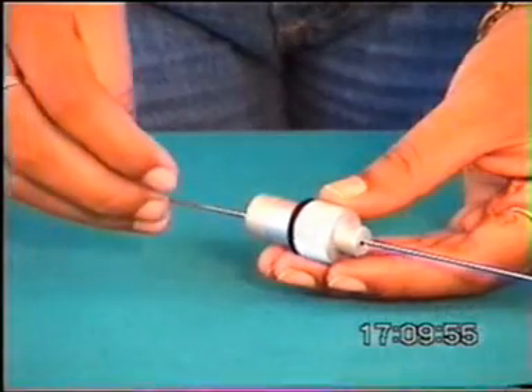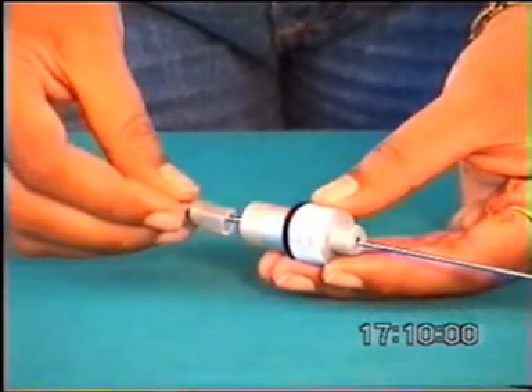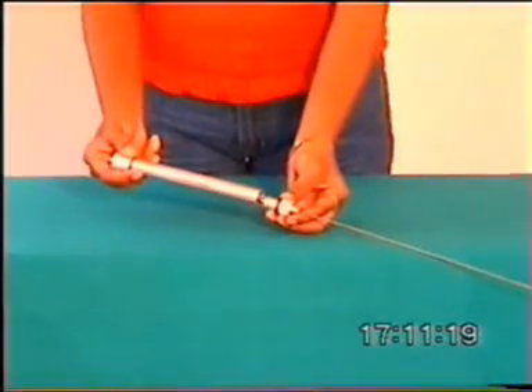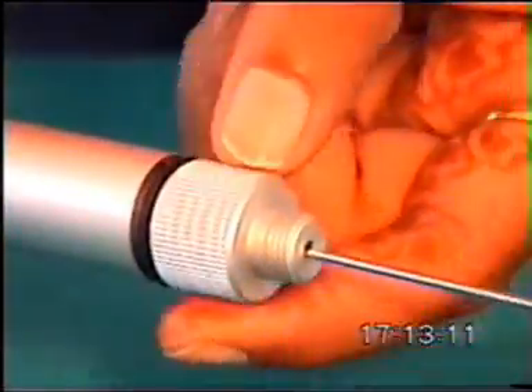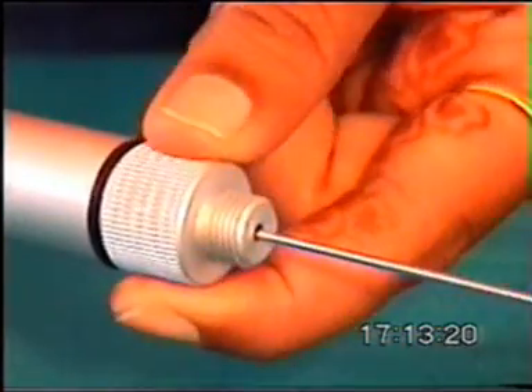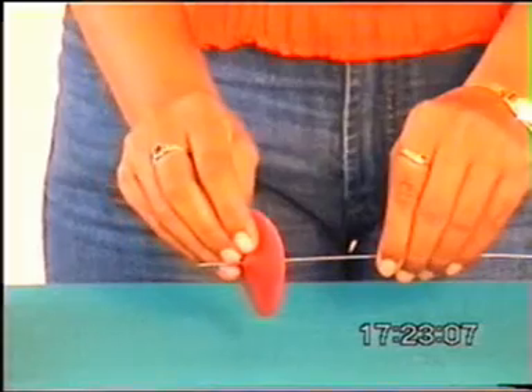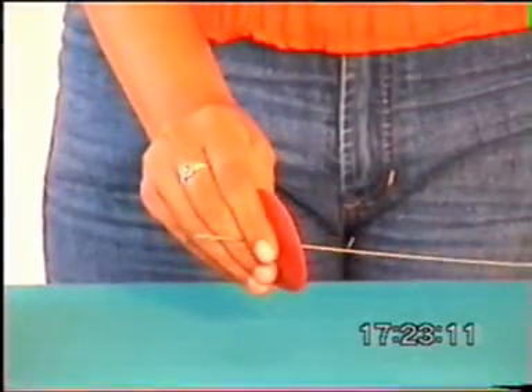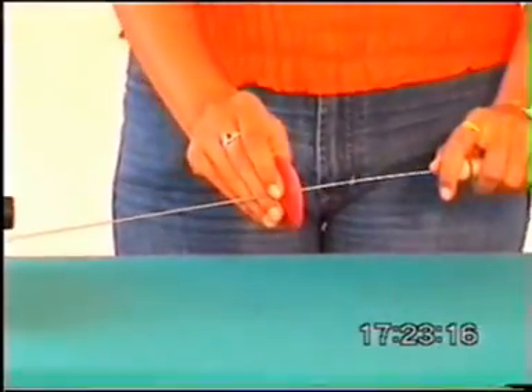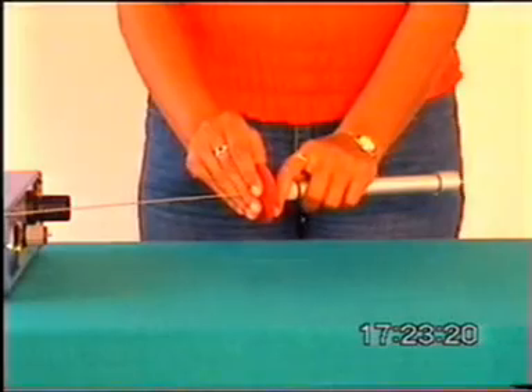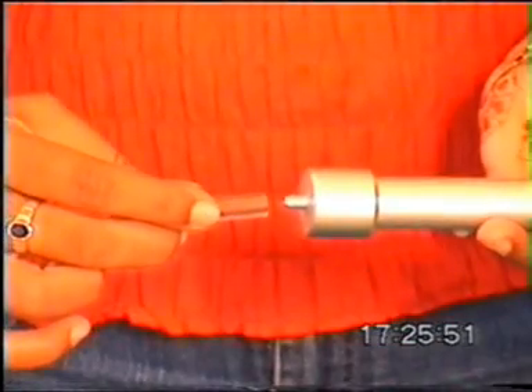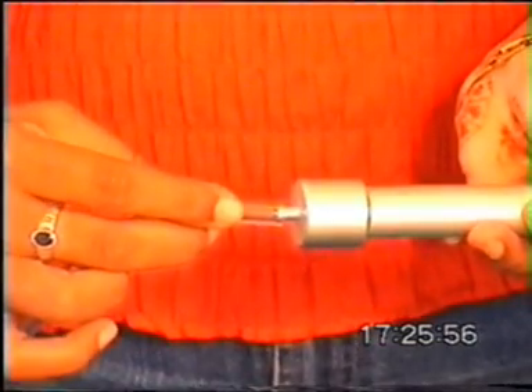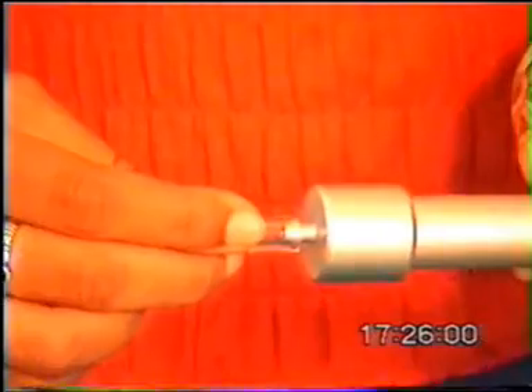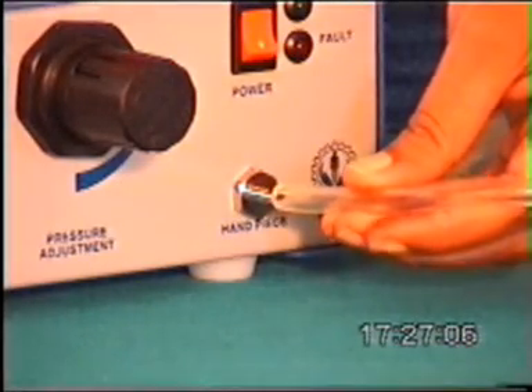A rubber O-ring is fitted onto the probe cover. A probe cover is then slid over the probe. Next, the probe cover along with the probe is screwed into the cylinder cover. A silicone dam is slid over the probe to prevent water from entering the handpiece. A tube is fitted to the inlet nozzle of the handpiece. The assembled handpiece is then connected to the control unit.